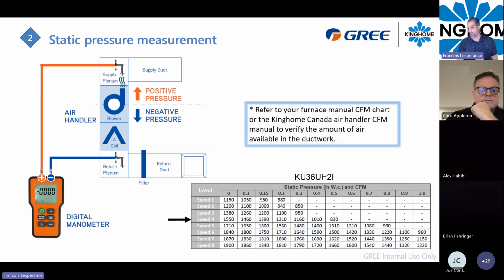Also, what is really important when you do your startup, or when everything is installed properly, is to take the static pressure measurement. You will need your digital manometer and a static pressure tool to properly measure the static pressure between the return duct and the supply duct. The purpose of measuring the static pressure is to make sure you have the right amount of CFM going through the coil and the furnace. Either way, it's an air handler or it's a furnace.